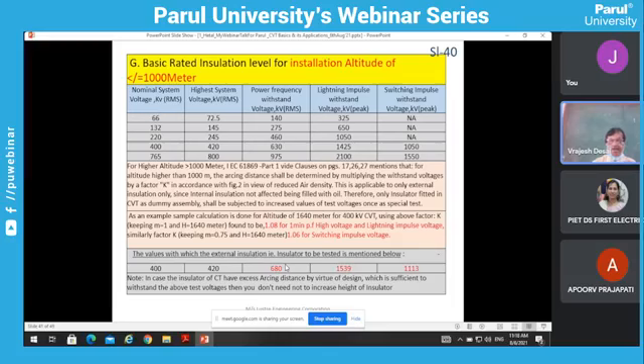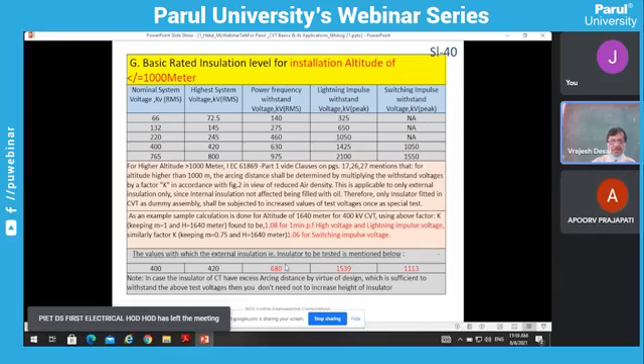Now, as you go to higher altitudes, like the Bhutan side, Darjeeling side or Himachal Pradesh, where the substations are located above 1,000 meters, right? When you go higher and higher, the air density reduces, so the withstand capability in air becomes more vulnerable to arcing. So you have to increase the arcing distance. You have to connect an insulator with a higher height, keeping the internal insulation as it is. The internal insulation is already with oil and capacitor inside, so it doesn't get affected. Only the external insulator needs to be upgraded to meet the higher altitudes.